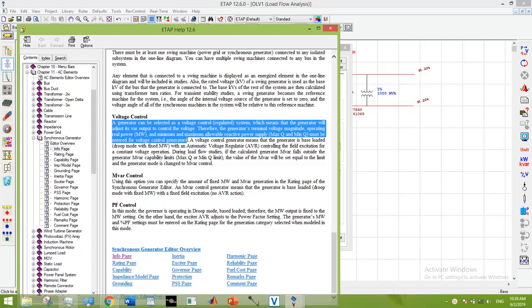We face the underexcited and underpowered issue for this voltage control generator because we were actually missing the data which would have been fed before running the load flow. It's not too late, let's enter the data now.